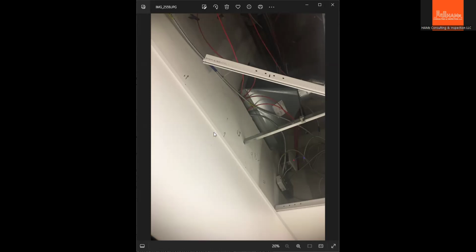Or in case this is a fire rated wall, you need to have a retaining angle and a fire damper, a protection inside of the duct, so that it will prevent the spread of fire or smoke to the other side. So it's a prevention for the fire to spread quickly. So that's a side step. I'm not going to discuss that. That's another inspection category.